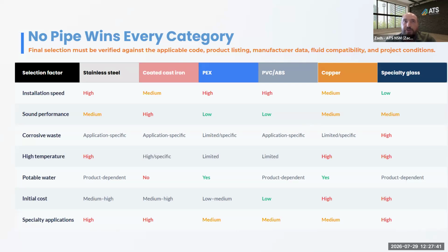But in healthcare, where you might see a 180 degree Fahrenheit spike, having those high temperature performance products is critical. Same with stainless steel for certain food preparation or brewery applications, where you have a dump load of high temperature into your drainage and it needs to handle that without causing cracking in the surrounding area.